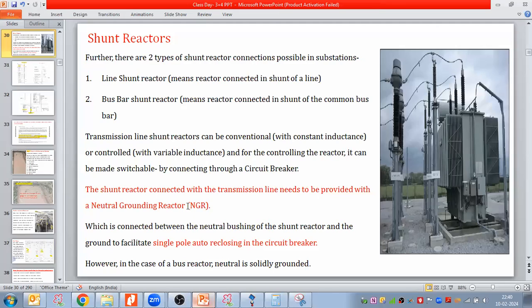And later on, once the system was ready, all of a sudden the NGR requirement came into the picture. So the company realized that this should have been mentioned in the scope of work, but by mistake they did not mention it, and they were not aware of this neutral grounding reactor requirement. Due to that reason, I took up this NGR dedicatedly in this discussion, so that whenever you deal with reactors connected with the line, you keep in mind the neutral grounding reactor.